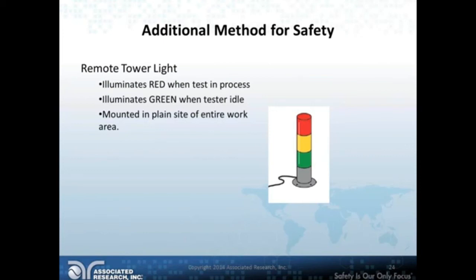And I usually see these mounted way up high on a production floor. It's not really for the test operator. He knows when he's going to run the test. It's for the guys around that might not know he's running a high-pot test. So if he sees, oh hey, the light's red, Jim's working on a high-pot test, I better wait till that's over before I go in there and talk to him.